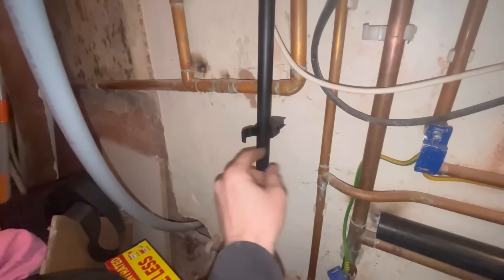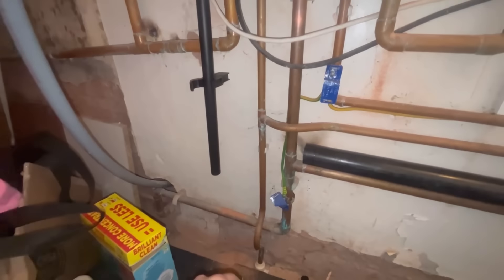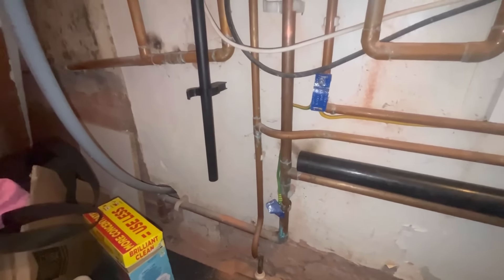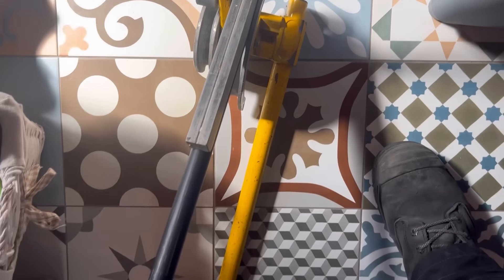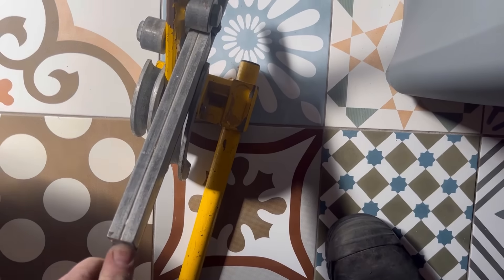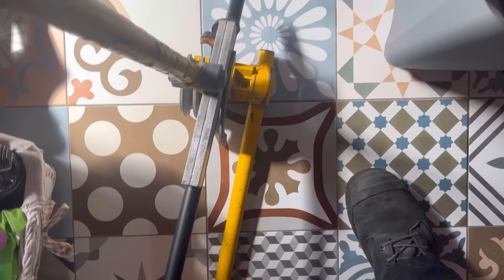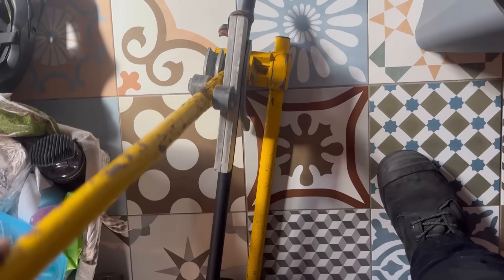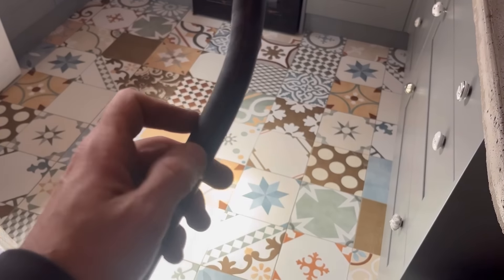All right, so we've come straight to the condensate connection there at the back. Three spacer clips, big long screw, and now it's down. Now we need to get around this pipe here, so I've got an idea — do you know this? You can actually bend the condensate pipe. Put it in the pipe bender and just move it off. Cut the excess off and you just need to manipulate it — slowly bend it and eventually you'll get a bend on it just like that.